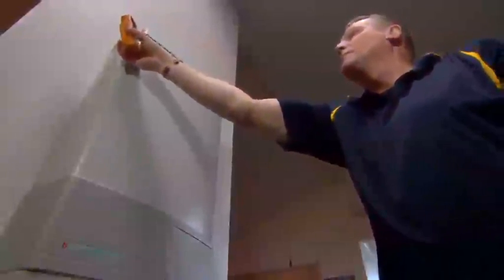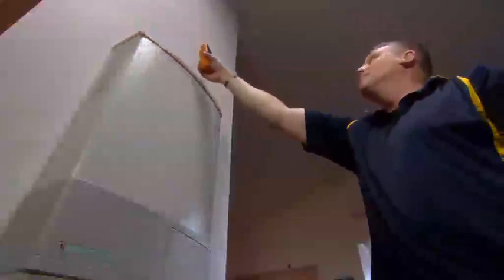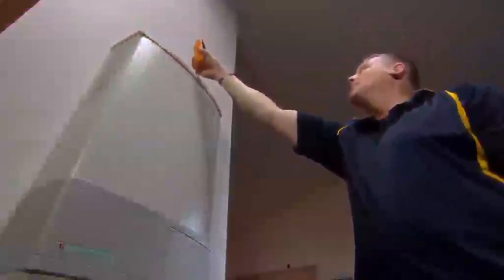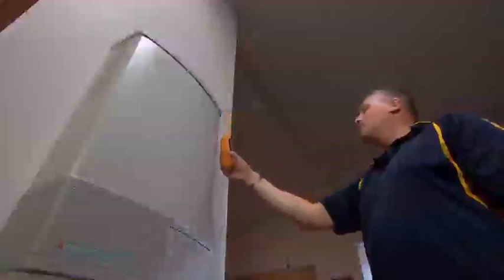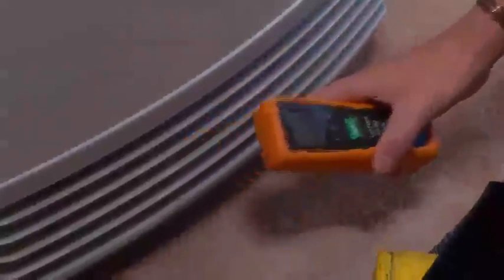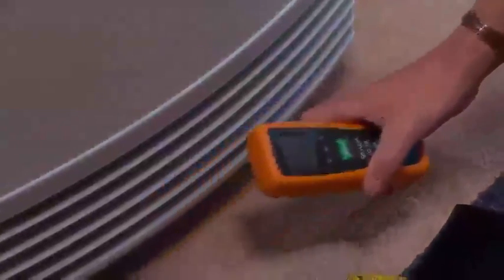If any CO reading is detected, it will mean a negative pressure within the building has been created by the exhaust fans, and flue products are being drawn back down the flue and dispersed into the building. To prevent negative pressure developing in the building due to the operation of exhaust and extraction fans, increased ventilation from outside the building through walls, floors, or ceiling space is needed.